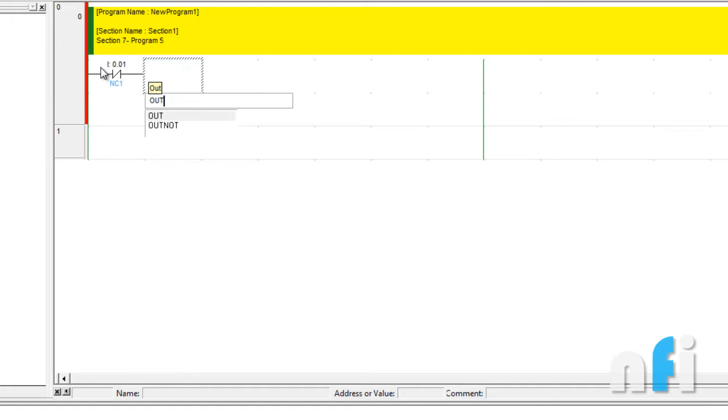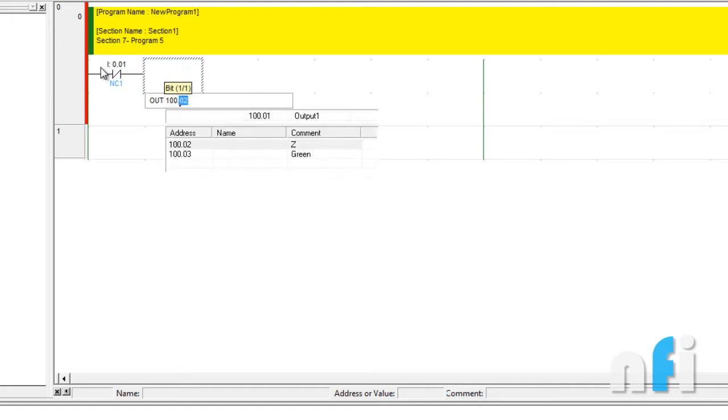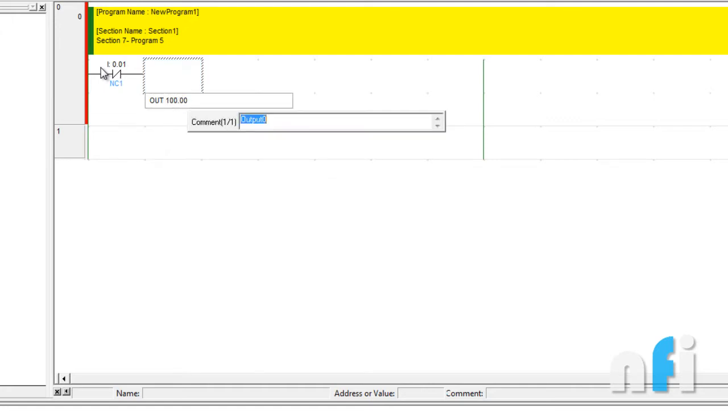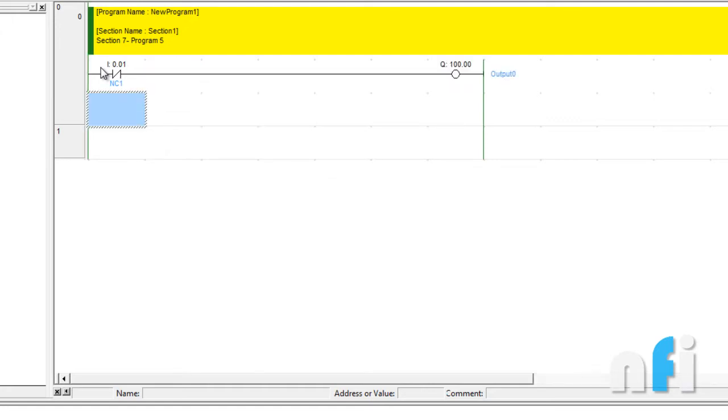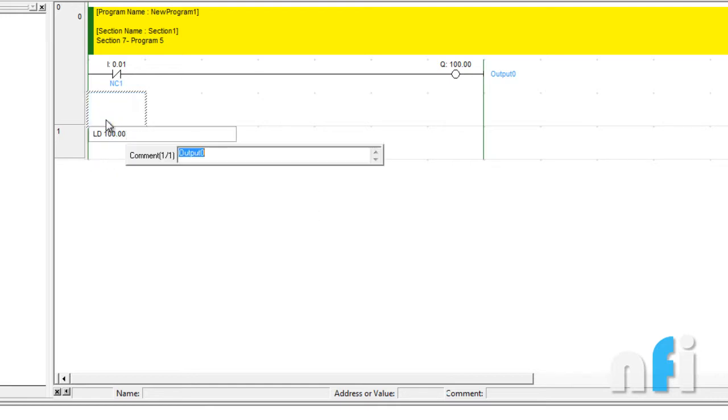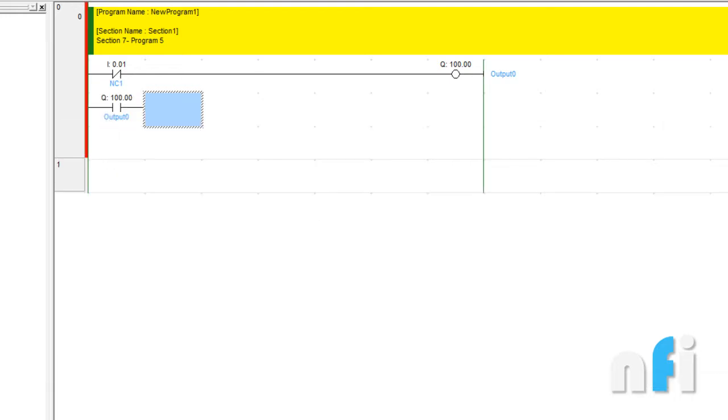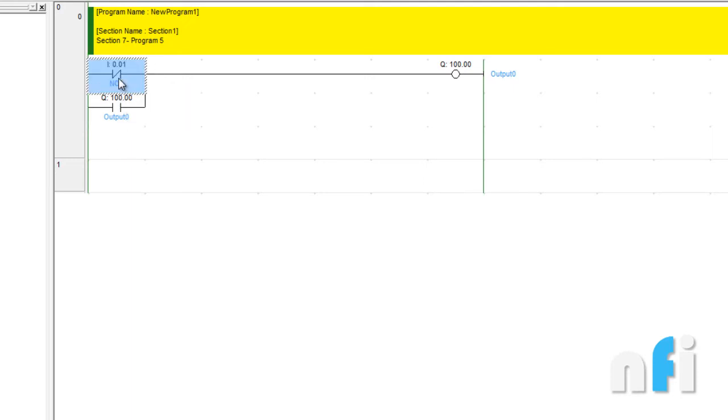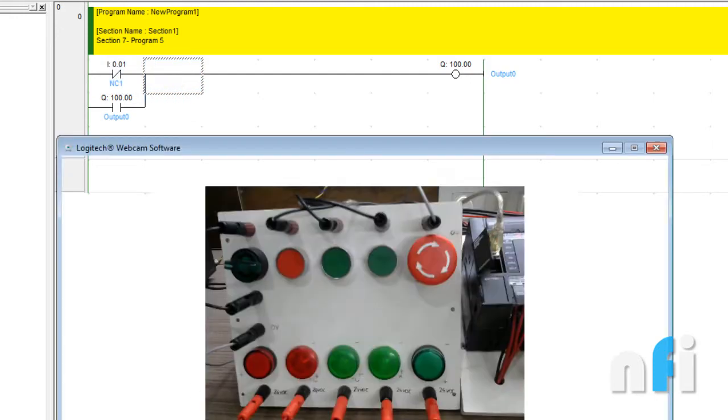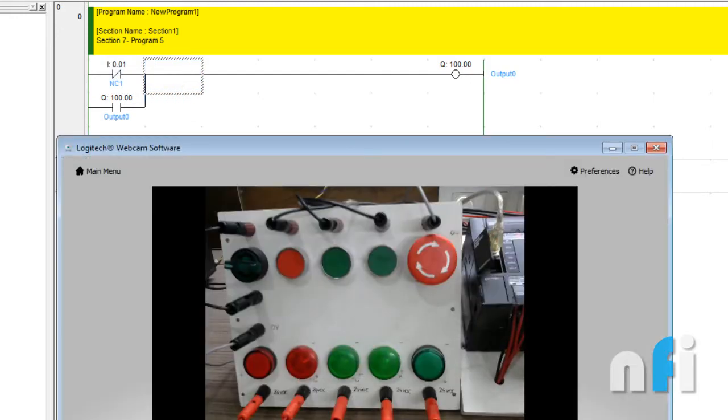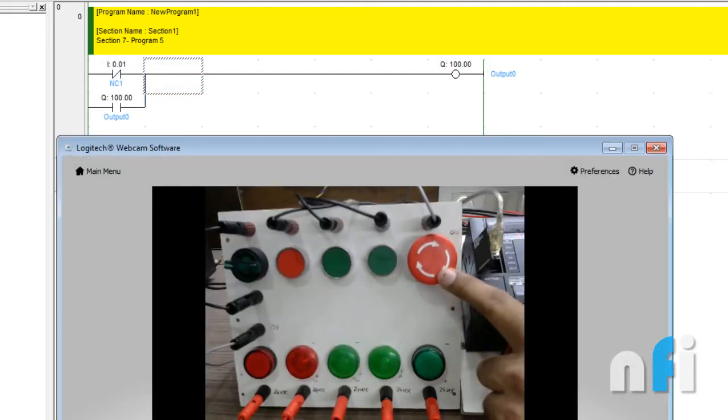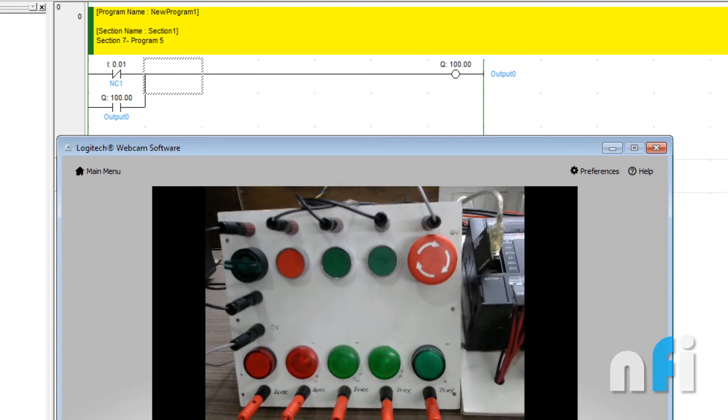Then I'll write OUT Q 100.0. This is my first output. To latch the output, I'll be using LD not Q 100.0 as an output. It's very simple based on our earlier concept—we have used NC to latch, so we'll be using NC here.